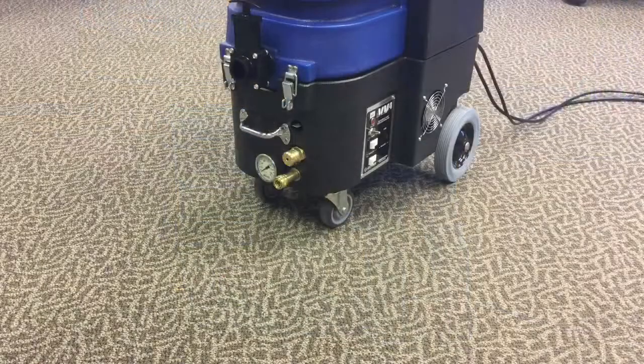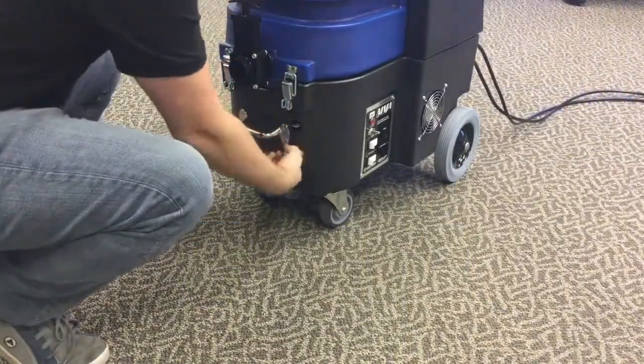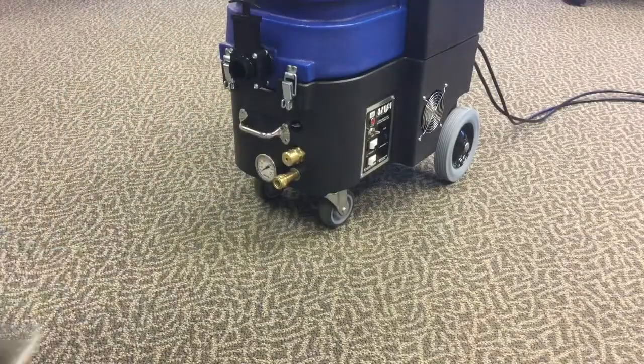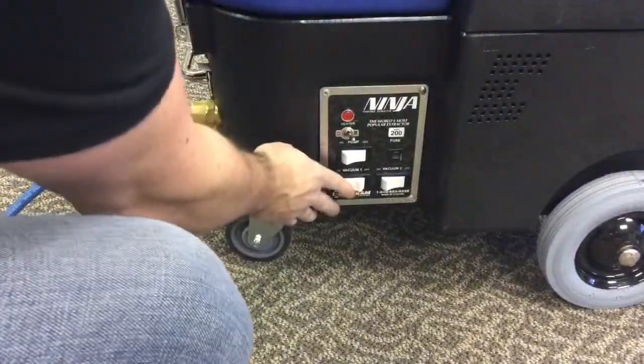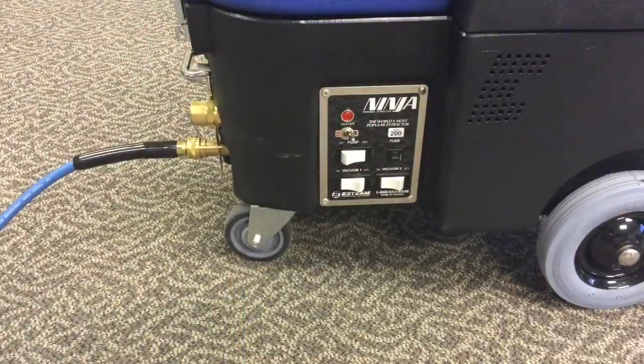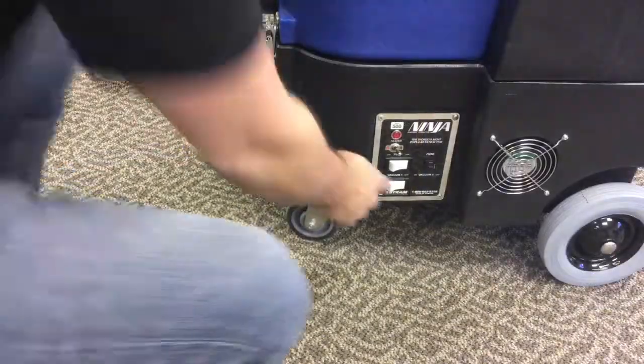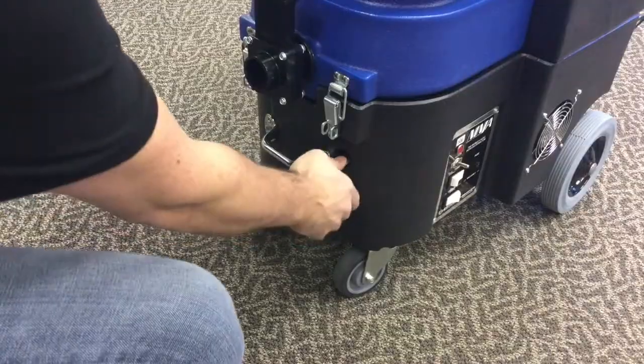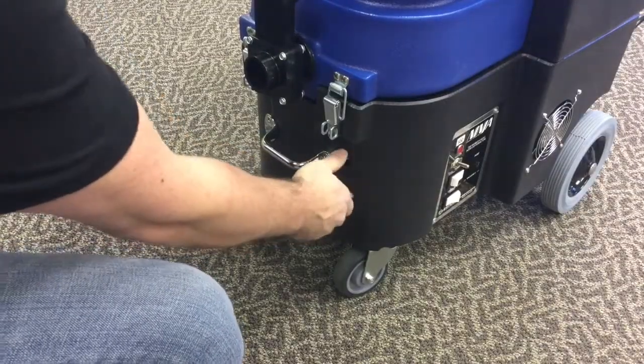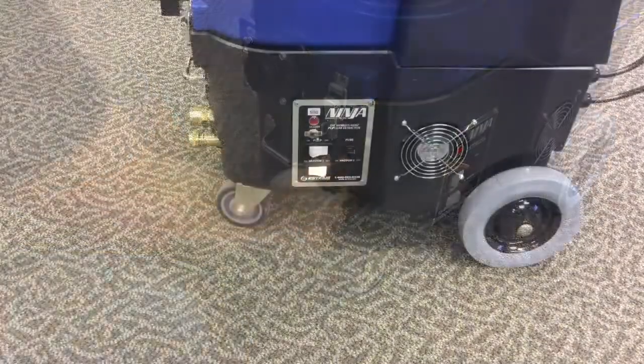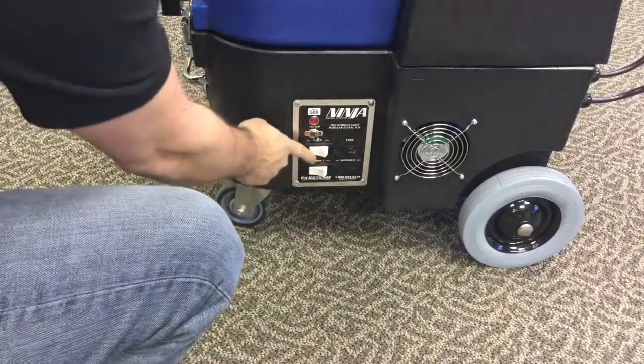To prime your pump before use, make sure that the pressure regulator is turned down to a lower PSI pressure setting. For the Ninja 200 model, switch both vac motor buttons to the on position. Ninja 500, switch the 1 vac motor button to the on position. Press and release the primer valve to relieve any pressure on the water lines and pump head prior to turning on the pump. Switch your pump switch to the on position.